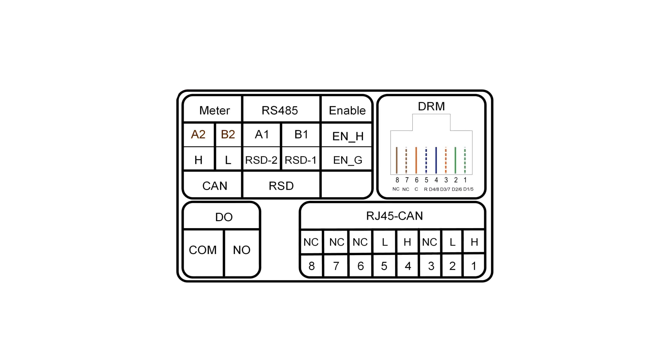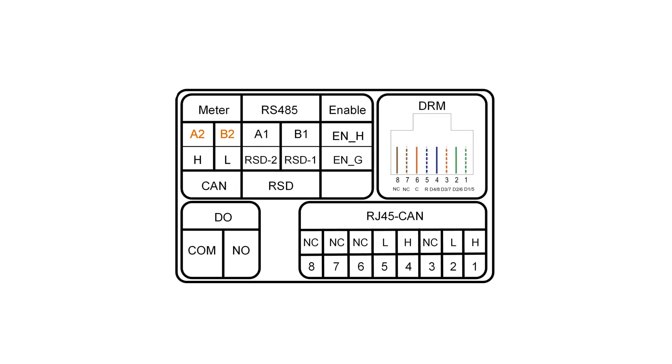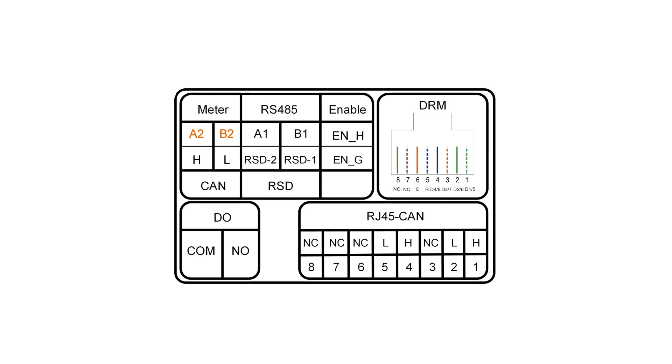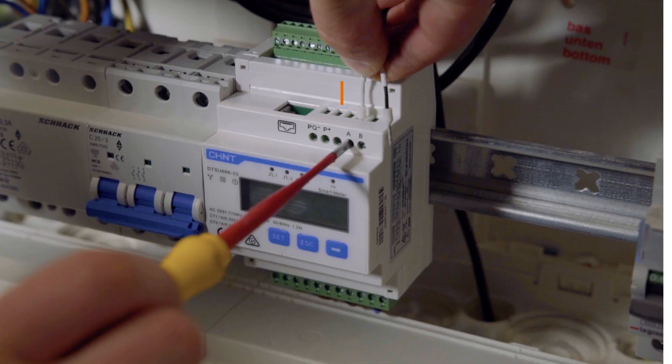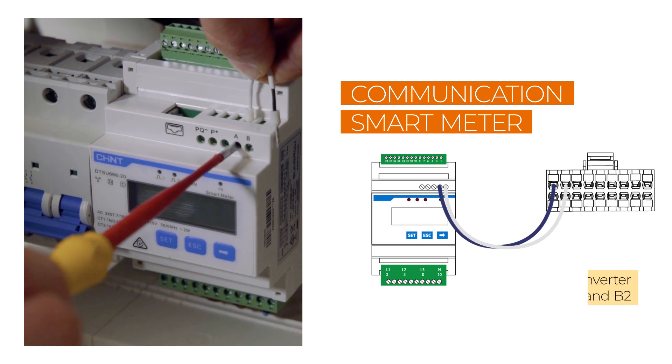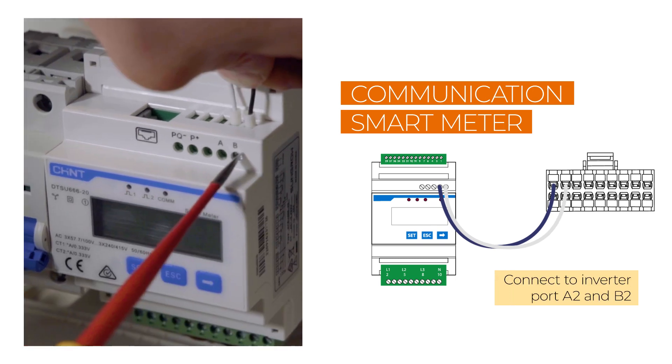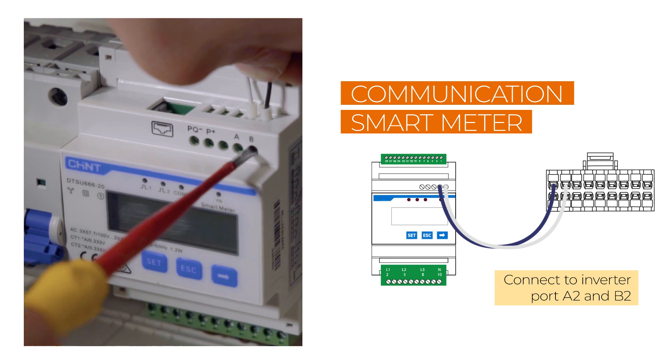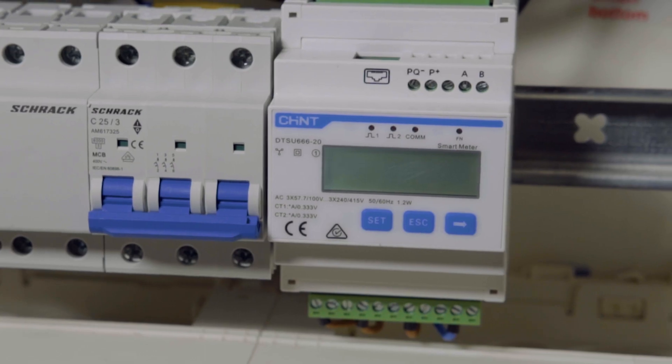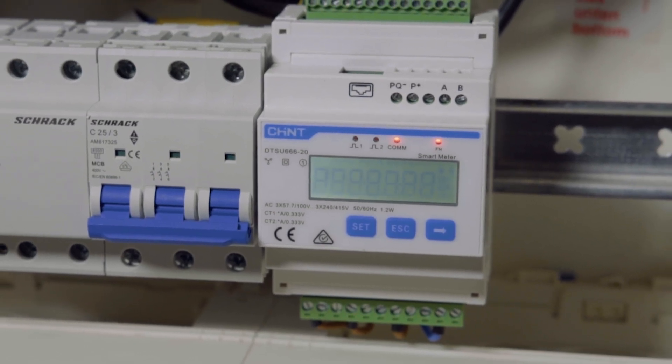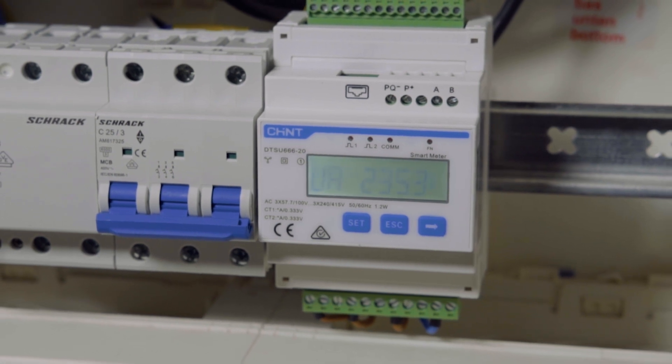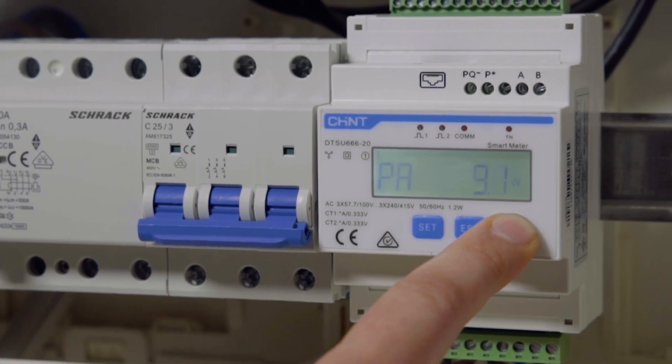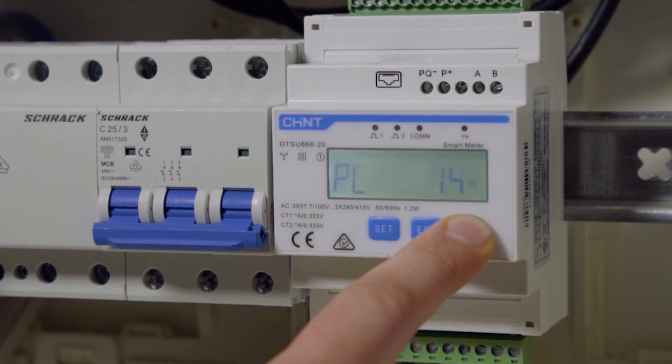At the bottom of the inverter, above the communication connector, you will find a table with information about which cable has to be plugged into which port. The smart meter is connected from the meter port A to the inverter port A2 and from the meter port B to the inverter port B2. No settings in iSolar Cloud are required. Once the meter is correctly connected to the three-phase hybrid inverter, it will be automatically recognized.